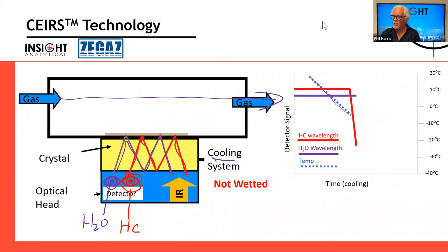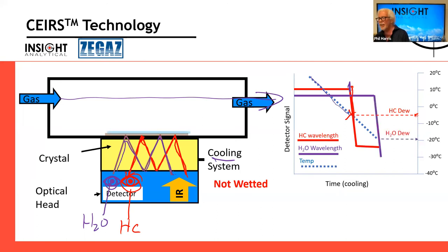So as the crystal cools in this case, it gets to here and it hits the hydrocarbon dew point temperature. The wavelength of light interacting with the hydrocarbons drops off in intensity. That's what we're showing right here. The wavelength drops in intensity right when we hit this temperature. So we say, well, that temperature corresponds to the hydrocarbon dew point. We continue to cool the crystal. Hydrocarbons are condensing out. And when we hit a certain other temperature, water starts to condense on the surface. The wavelength of light associated with water suddenly drops in intensity. And that tells us we just hit the water dew point.